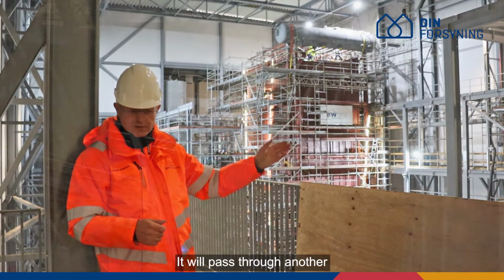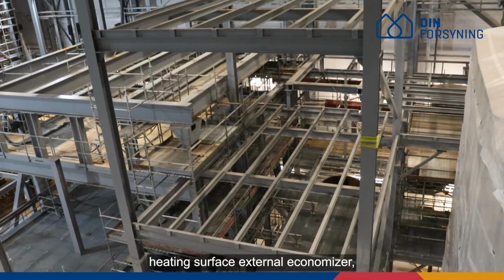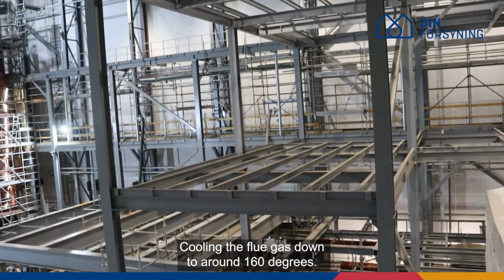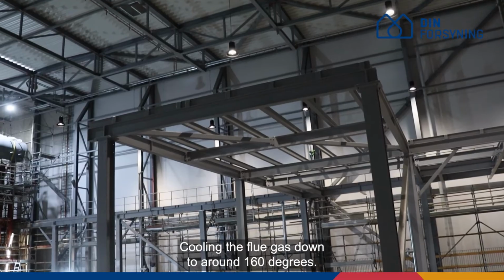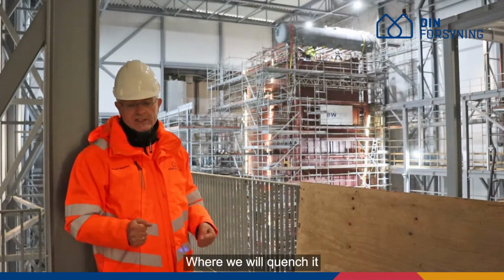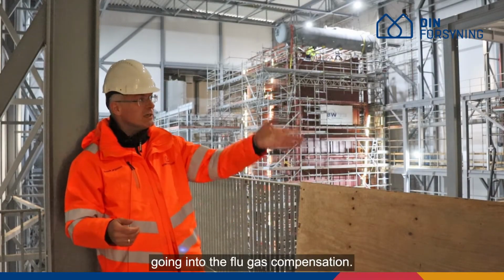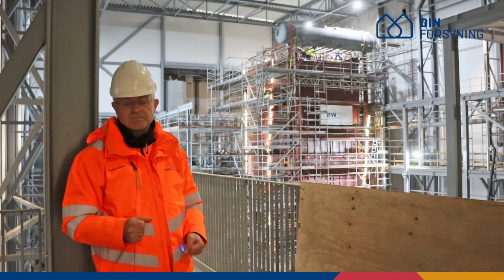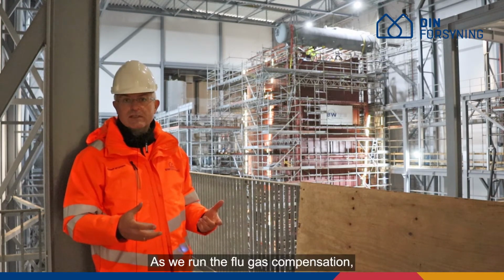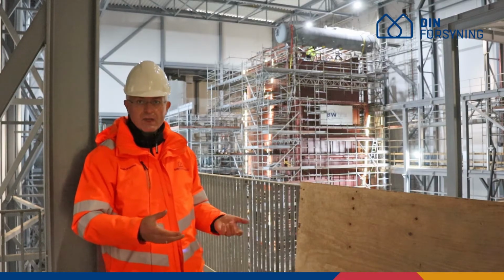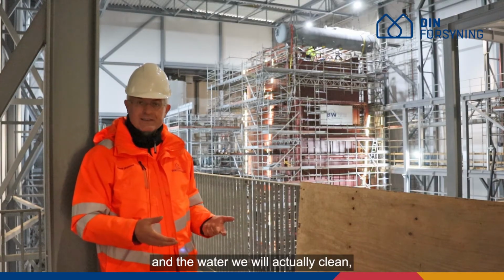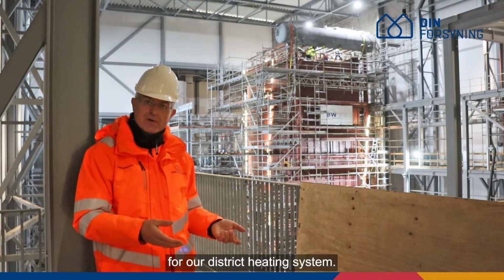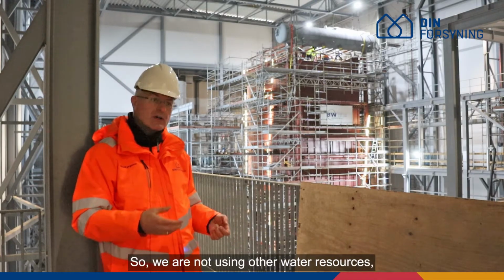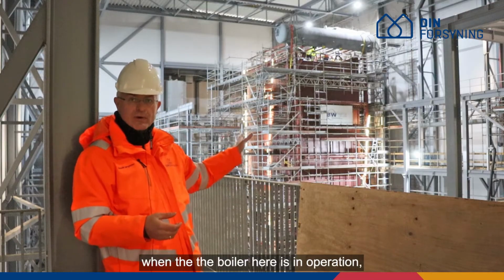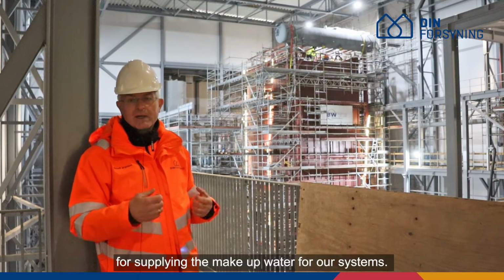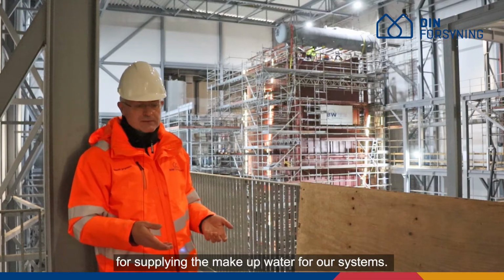passing through another heating surface, external economizer as we call it, cooling the flue gas down to around 160 degrees, where we will quench it with additional water going into the flue gas condensation. And as we run the flue gas condensation, we will produce water. And the water we will actually clean to use as makeup water for our district heating system. So we are not using other water resources when the boiler here is in operation for supplying the makeup water for our systems.